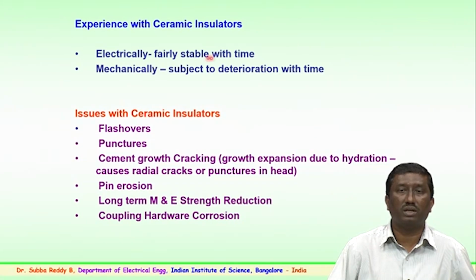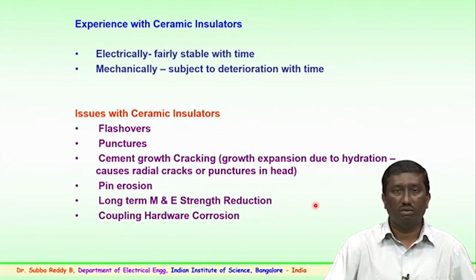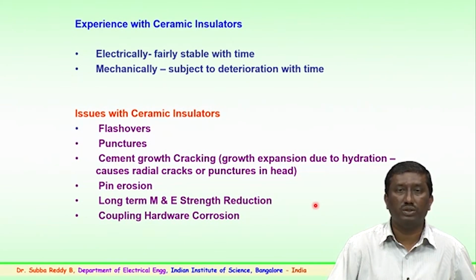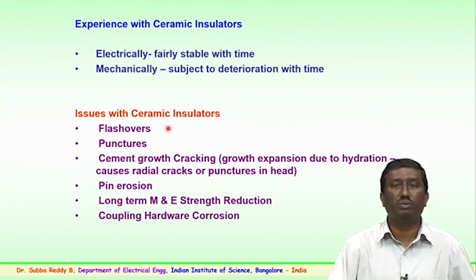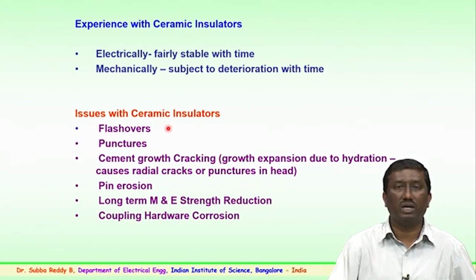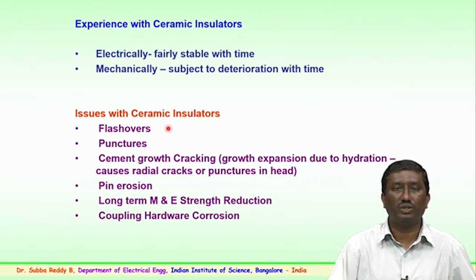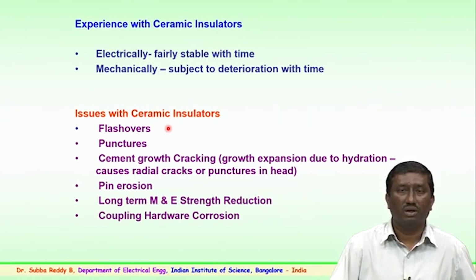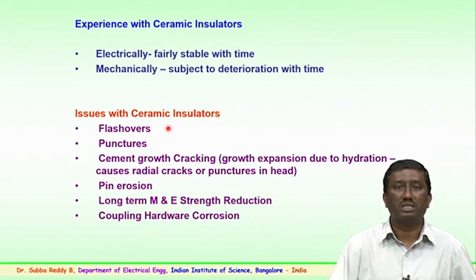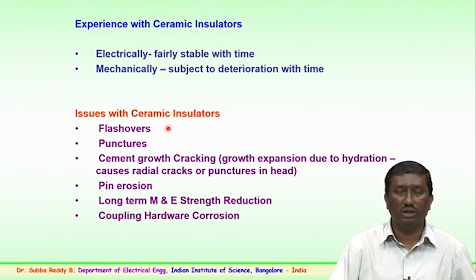So, these are some of the things that mechanically could subject the insulator to deterioration over a long period of time. What are the issues with ceramic or porcelain insulators? One is flashovers. Flashover depends upon pollution or contaminated areas, where over a period of time contaminants collect on the insulator surface. In the dry season, the problem of flashover never happens. In case of fog, mist or early monsoon conditions, the surface becomes wet and starts conducting, and flashovers do happen.